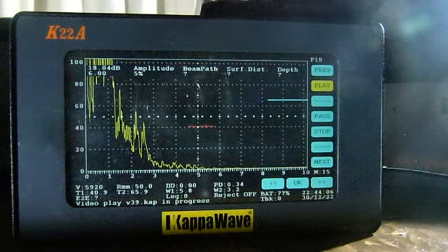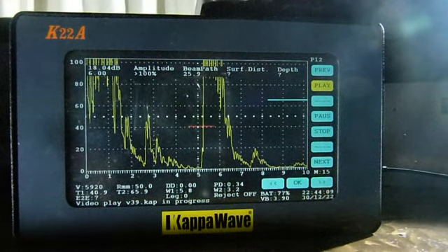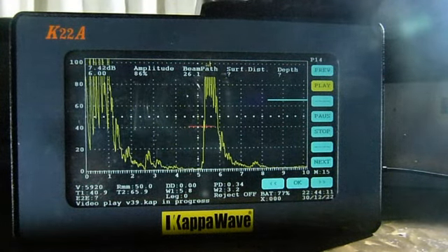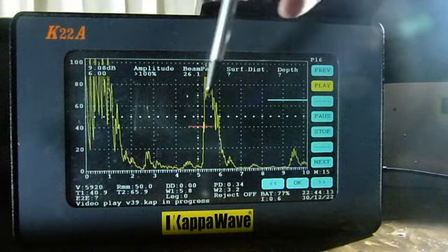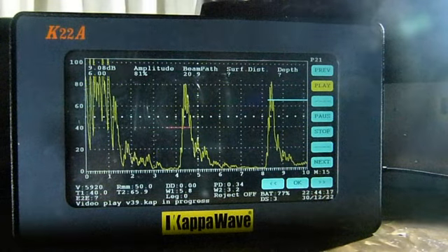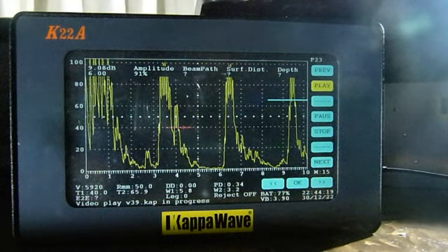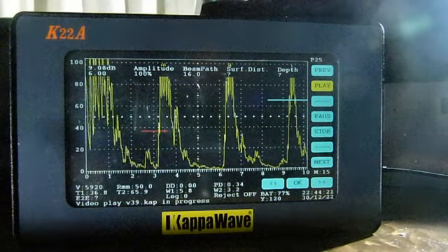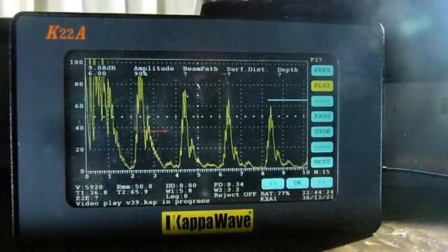We are now playing that file on a 50 mm range, and the amplitude changes, gate movements and defect indications are all very well recorded and played back. It's a joy to use this instrument to test, record and play the result. You may transfer the files to computer for further action.